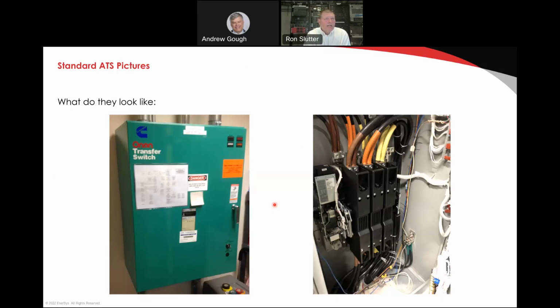We want to see that on the ATS so you can know where to get some information about what's going on. The picture on the right is the interior portion, which we talked about earlier. One thing to note here, it is never safe to open the ATS door unless you're a qualified electrician with PPE. Why? There's exposed live bus, as you can see there on the picture on the right.